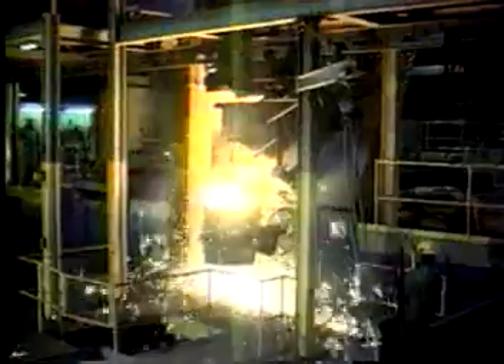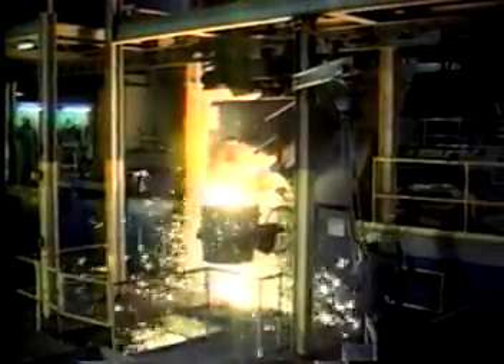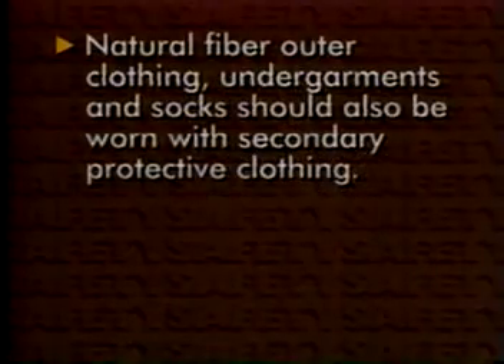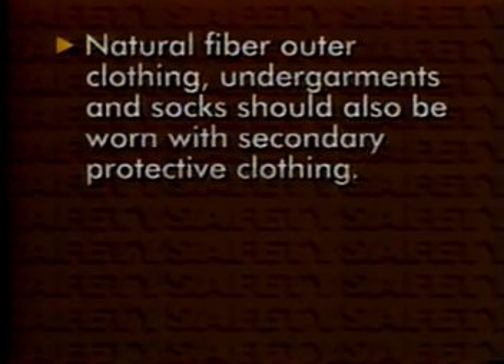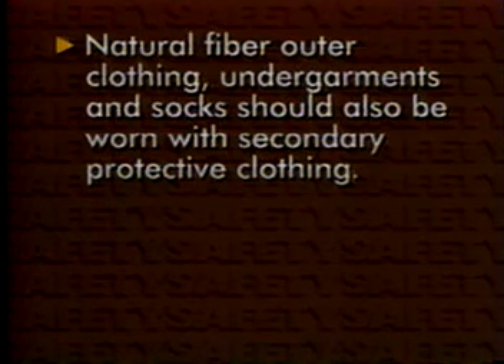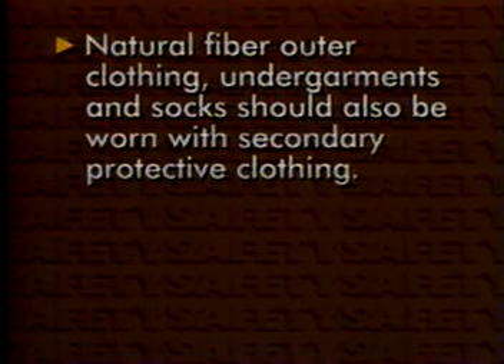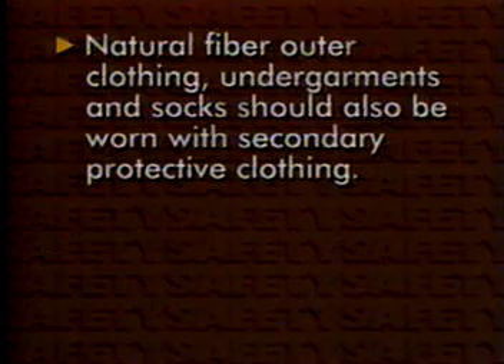In many cases, serious burns and fatalities have occurred because ordinary clothing caught fire from a small spark or splash, not because of burns caused directly by molten metal. Along with secondary protective clothing, you also should wear natural fiber outer clothing, undergarments, and socks. Some synthetic fabrics melt or catch fire, and this can increase the burn hazard. Safety clothing suppliers recommend the use of washable, fire-resistant undergarments.